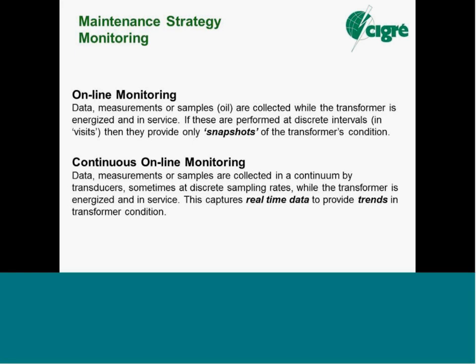I pointed out a little earlier, which this slide is reinforcing, that online monitoring simply means... just what do we mean by online monitoring? We realised that there's a distinction to be made between continuous online monitoring and what is generally online monitoring. Online monitoring is any sort of monitoring we do when the transformer is online. It doesn't necessarily mean what the next slide refers to, and that is continuous monitoring, usually with a clever device involved, transducers, maybe coupled with an intelligent electronic device, an IED, to do some interpretation for us.